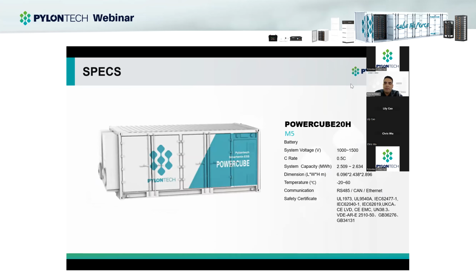Then we have this 20 feet container as well, but for the M5, which is our biggest battery. For this system, we can have the voltage from 1000 to 1500 volts. This can also go up to 0.5C, so maybe we can have the discharge for 2 hours, and the capacity of this container can run from 2.5 to 2.6 megawatt hours.